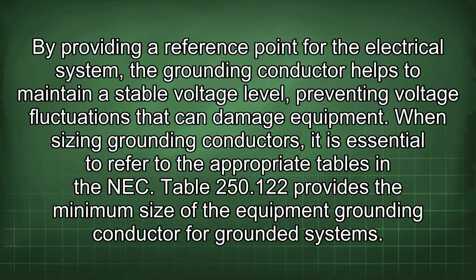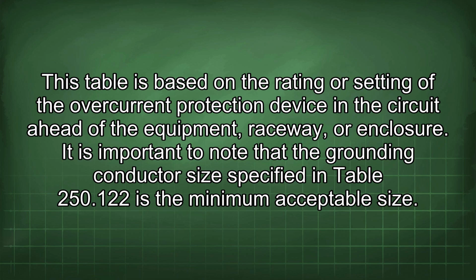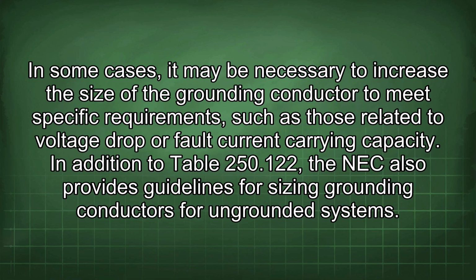When sizing grounding conductors, it is essential to refer to the appropriate tables in the NEC. Table 250.122 provides the minimum size of the equipment grounding conductor for grounded systems. This table is based on the rating or setting of the overcurrent protection device in the circuit ahead of the equipment, raceway, or enclosure. It is important to note that the grounding conductor size specified in Table 250.122 is the minimum acceptable size. In some cases, it may be necessary to increase the size of the grounding conductor to meet specific requirements, such as those related to voltage drop or fault current carrying capacity.